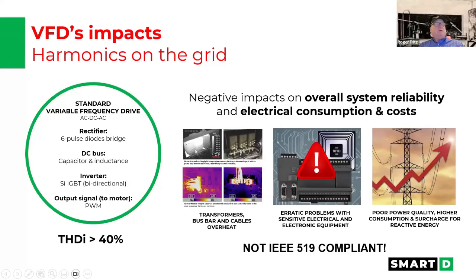We've done a lot of work for even PepsiCo, and with this 40% total harmonic distortion that is coming out of drives, by the time you've got multiple drives in there, like 30 or 40 of them, the whole building becomes higher and higher noise, and it's not IEEE 519 compliant.